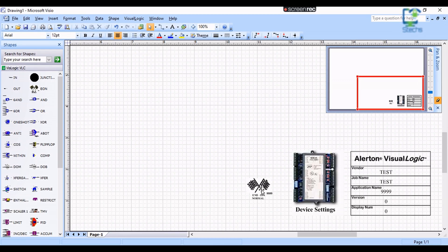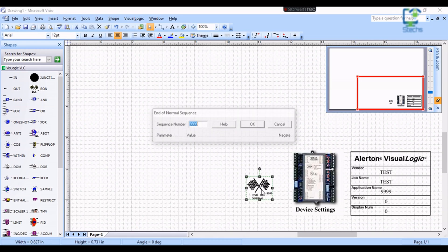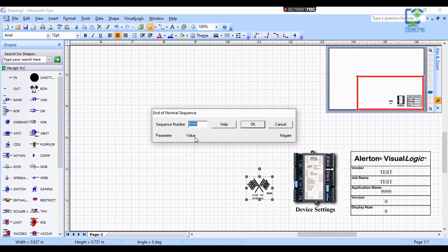The third block with flags is for End of Normal Sequence. We must enter the last sequence number for the functional blocks we are going to use in the program. Here I am entering 9999, which is the last sequence number. If you don't set this number the program cannot be read by the controller.